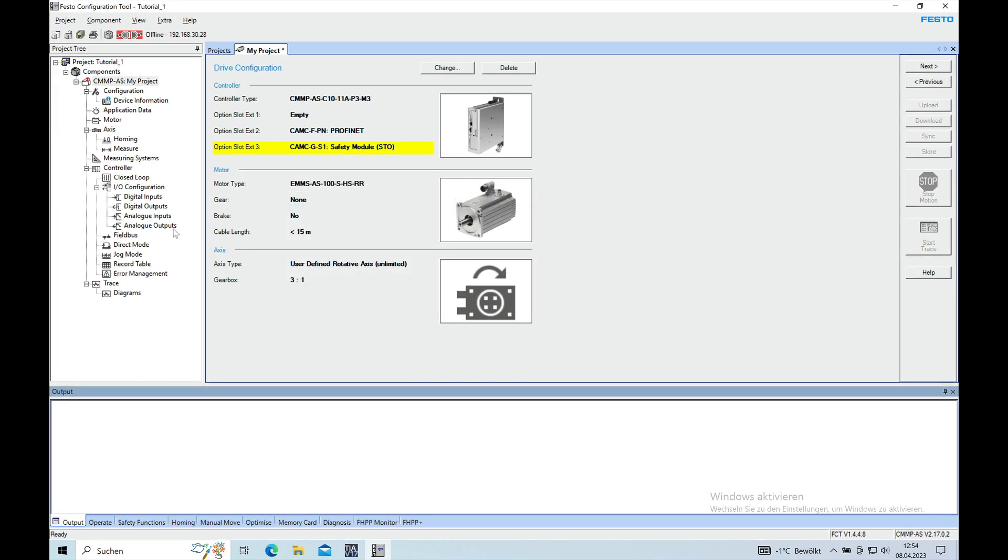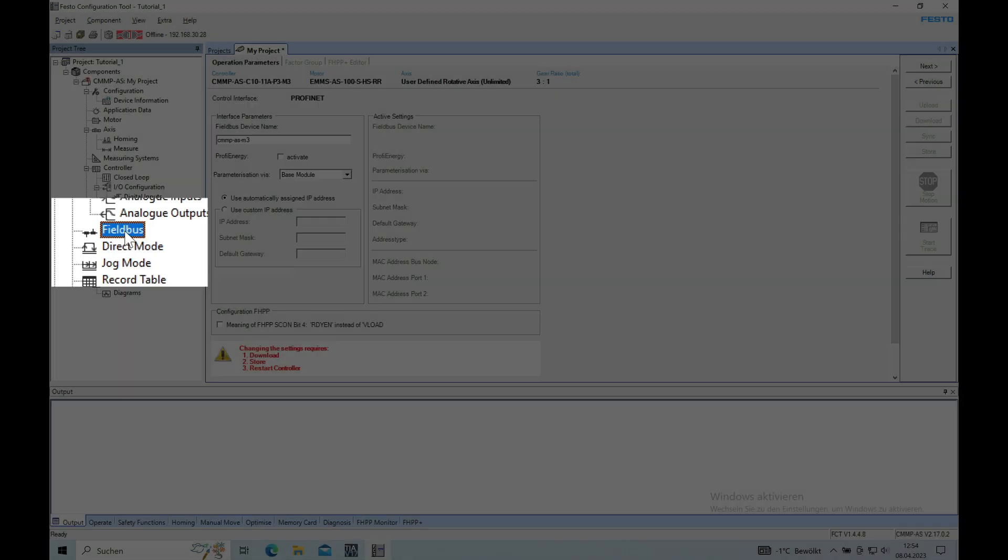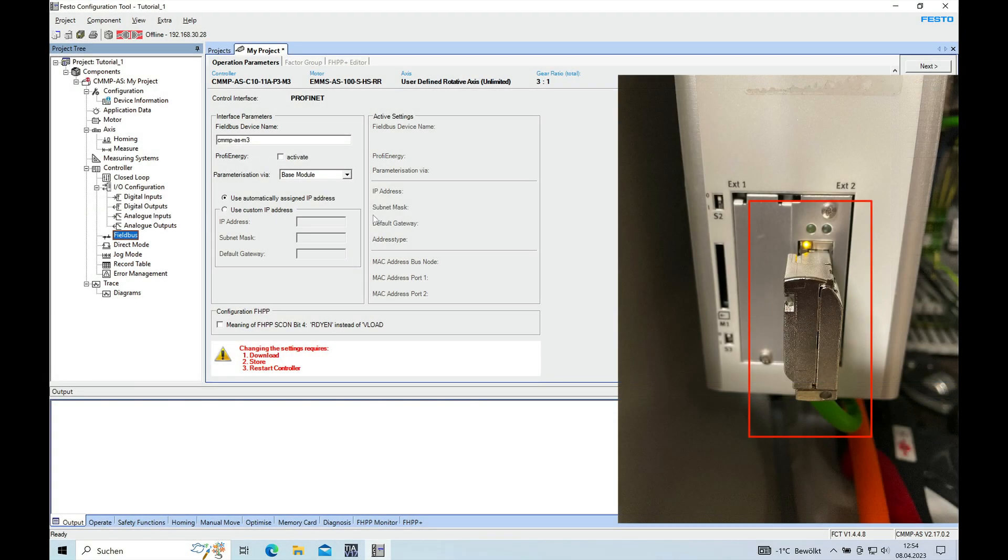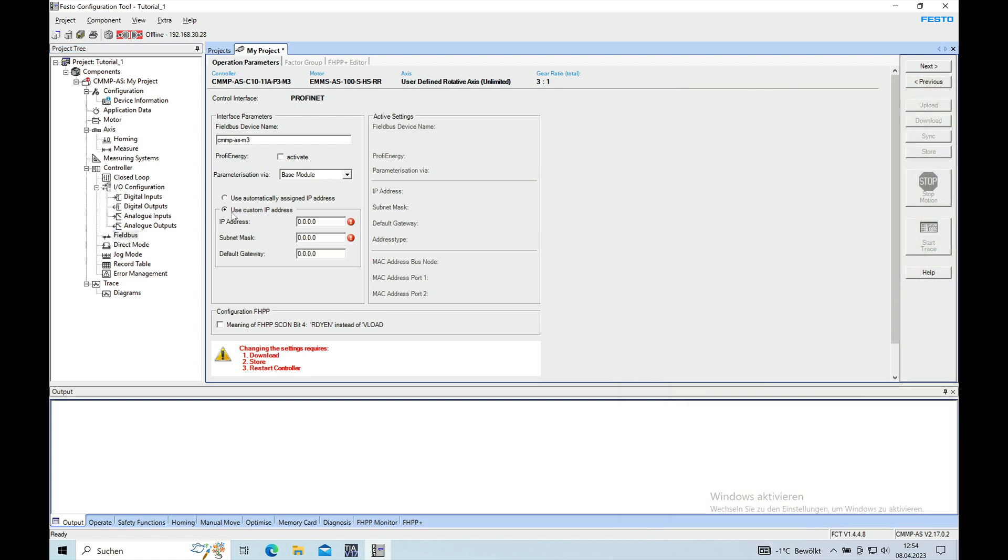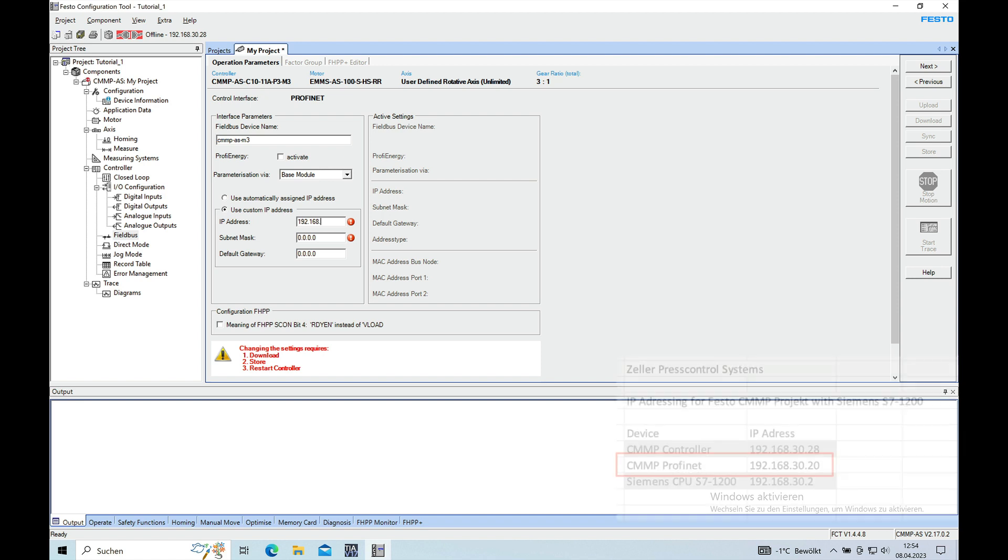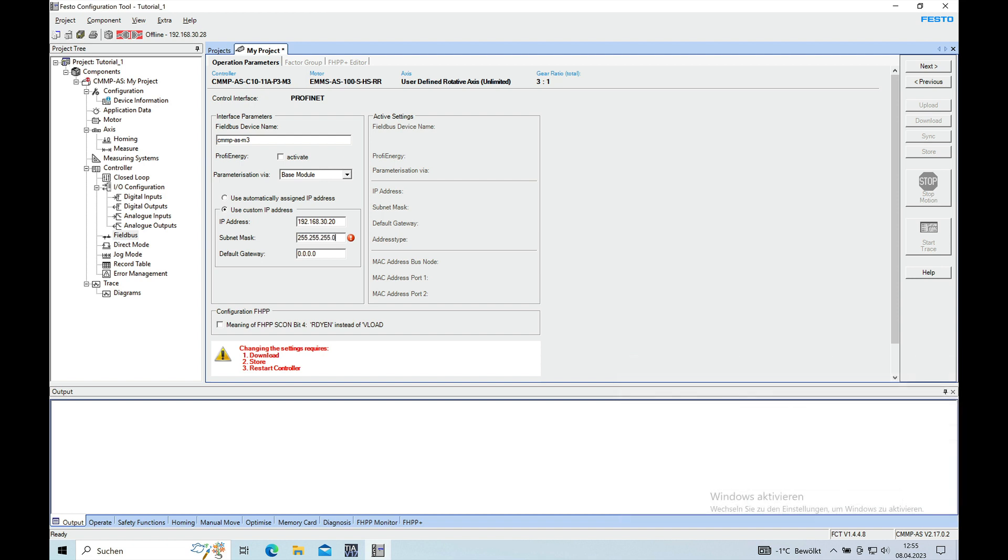As the next step, you want to go to the field bus configuration. Then here in this section right here in the middle, you can give the CMMP the IP address for the Profinet network that you are using. CMMP is address 20, subnet 255.255.255.0, and you don't really need a gateway.